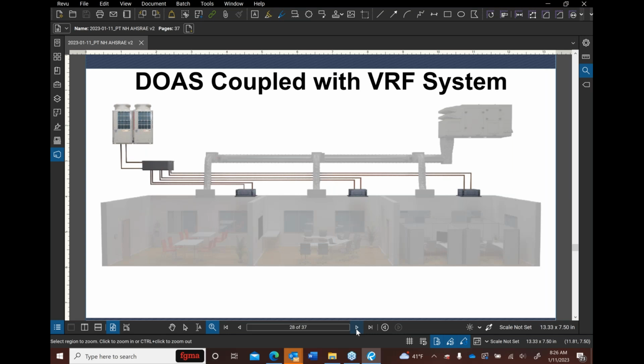One thing I'd like to just piggyback, if I could, for a minute, Jeff. So we were going through this delicate balancing act of what was the most efficient way to deliver the mechanical versus what could we actually achieve in terms of ceiling heights. As Jeff mentioned, we had very tight floor to roof structure clearance. I think it was just a little over 9 feet. But what we landed on was, like Jeff said, 3 classrooms being served by a DOAS unit.